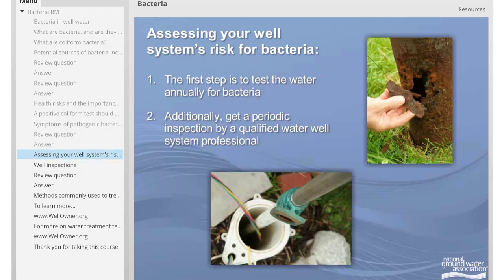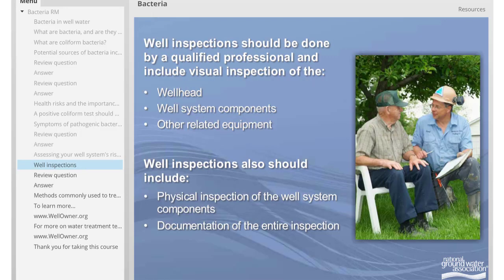It is important to assess the risk of your well system for bacterial contamination. The first and most important step is to test your water annually, at a minimum, for bacteria, and more often if symptoms indicate. Beyond a water test, you should get a periodic inspection by a qualified water well system professional. Consult with a professional as to when it is time to get a well inspection. An inspection should include a visual inspection of the well head, well system components, and other related equipment, as well as physical inspection of the well system components and documentation of the entire inspection.